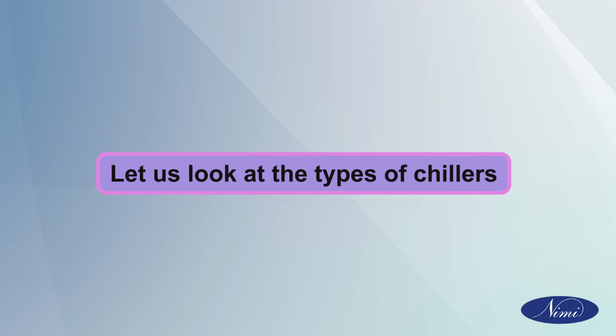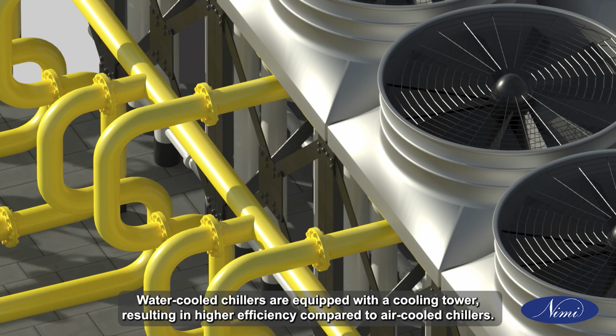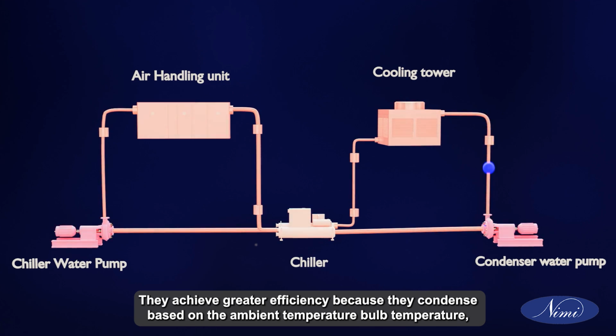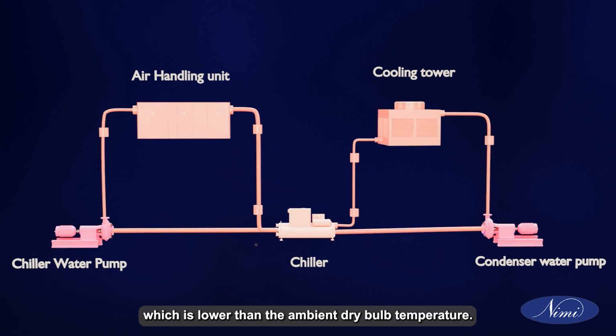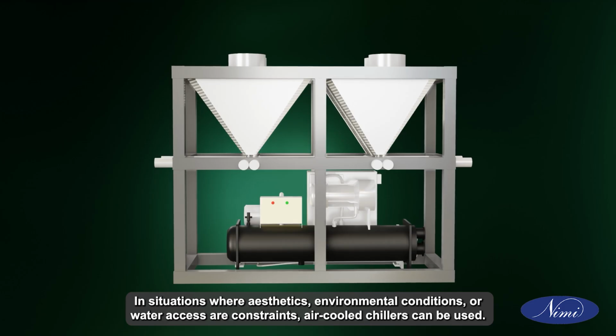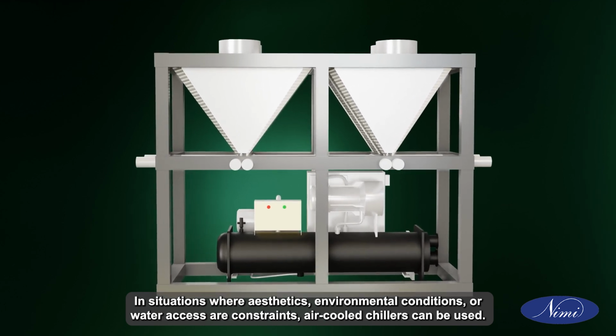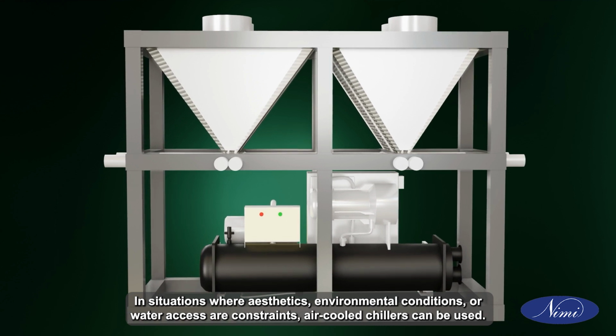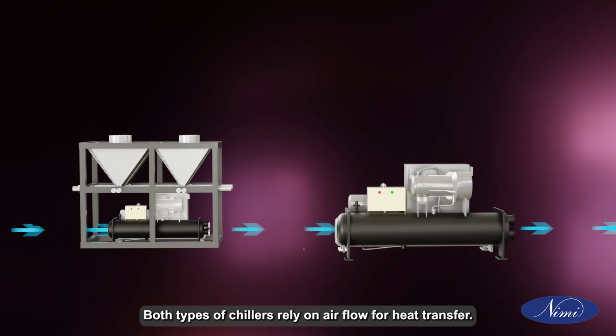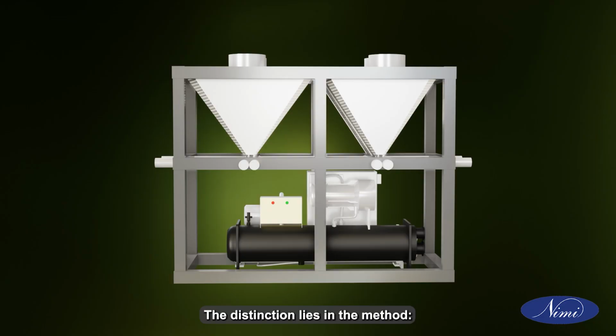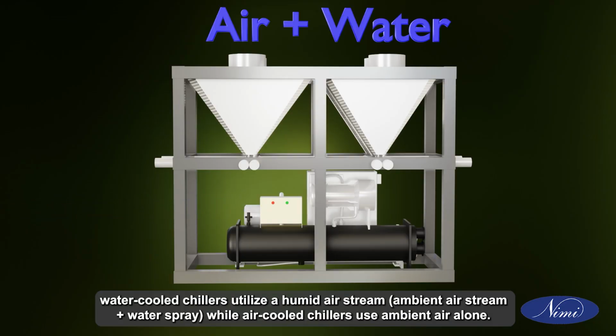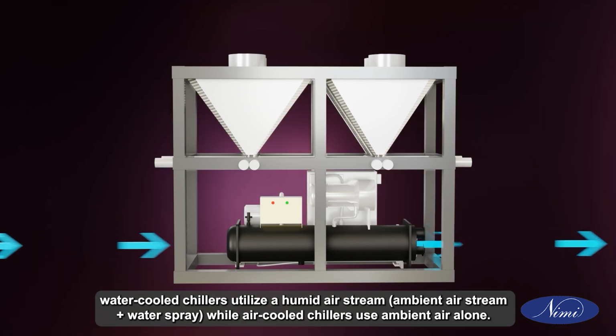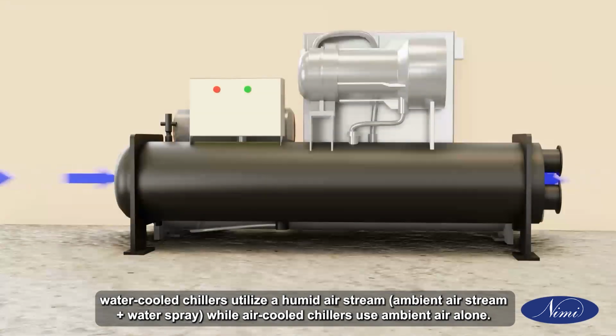Let us look at the types of chillers. Water-cooled chiller. Water-cooled chillers are equipped with a cooling tower, resulting in higher efficiency compared to air-cooled chillers. They achieve greater efficiency because they condense based on the ambient wet bulb temperature, which is lower than the ambient dry bulb temperature. Air-cooled chiller. In situations where aesthetics, environmental conditions, or water access are constraints, air-cooled chillers can be used. Both types of chillers rely on airflow for heat transfer. The distinction lies in the method. Water-cooled chillers utilize a humid air stream, ambient air stream plus water spray, while air-cooled chillers use ambient air alone.